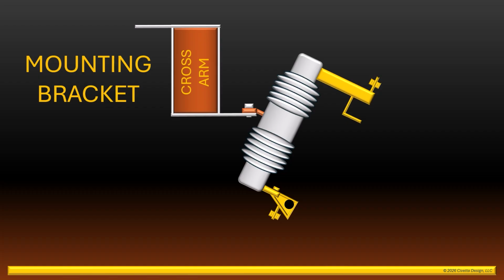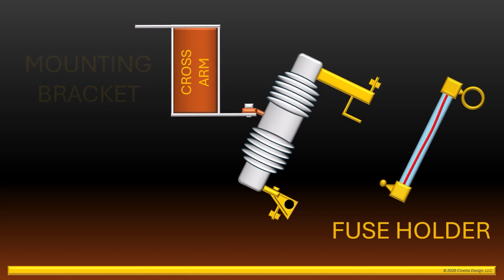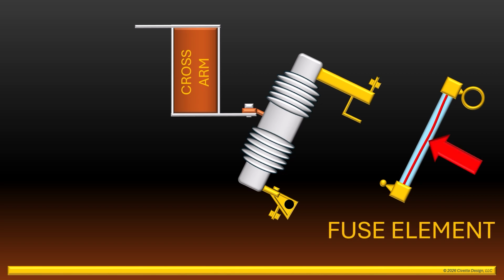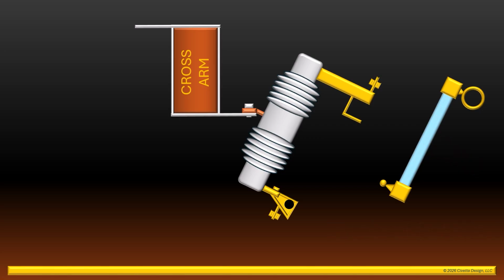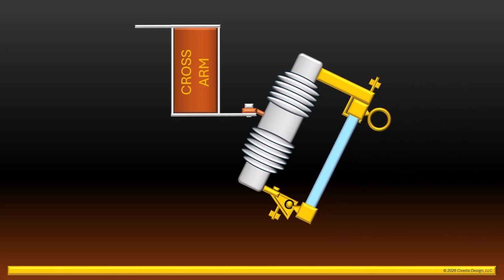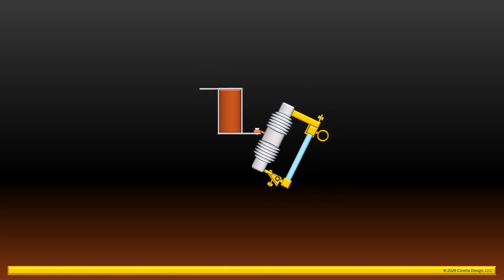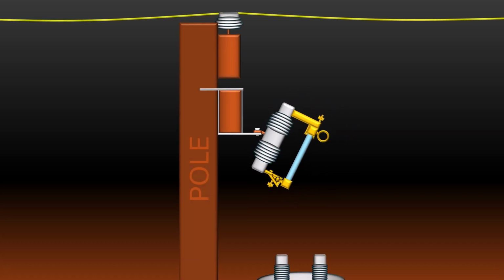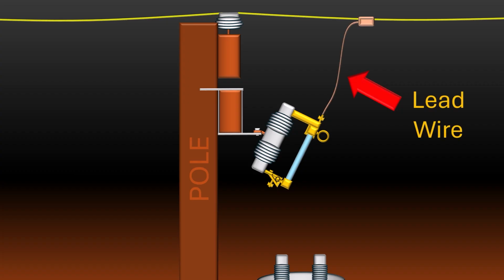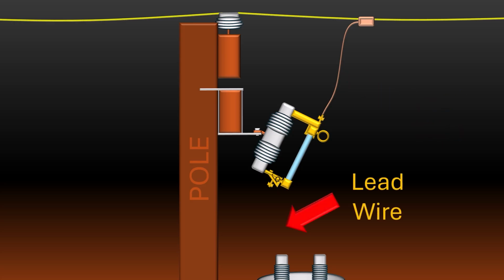The entire purpose of the cutout is to hold a high voltage fuse. The tube assembly shown at the right is a fuse holder. The actual fuse element is located inside the holder. The fuse holder is then attached to the cutout by a line worker. The cutout is typically connected to a primary phase conductor with a crimp or a wedge connector and a lead wire. The bottom of the cutout is connected to the primary bushing of the transformer with a second lead wire.